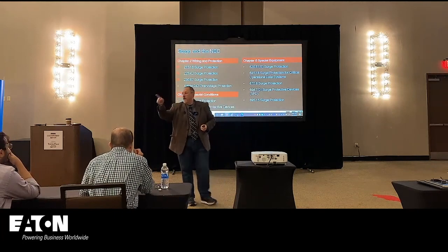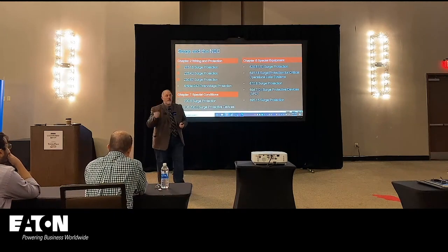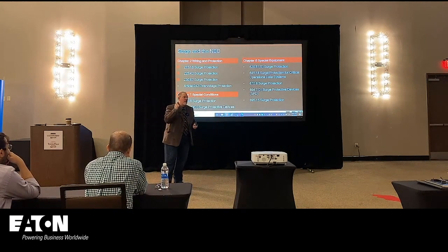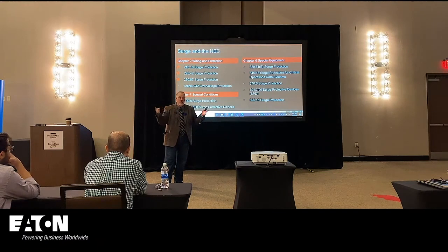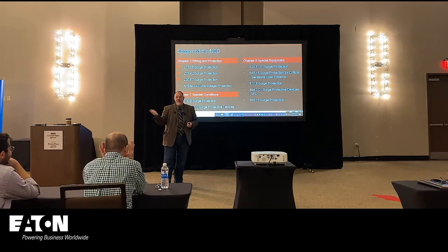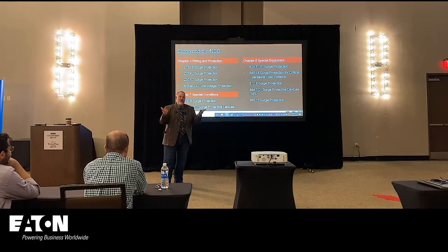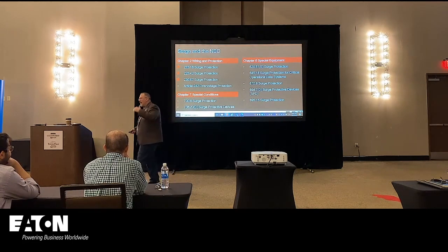And I know Dan Carnevale has a great demonstration as part of our experience center, where he demonstrates the lead length and the impact of every inch of lead length that you add between the surge device and the bus makes a big difference in let-through, right? I can sell you the product, but if you put it 10 feet away, I got the money and you don't have any value. So you want to make sure we apply surge products correctly.